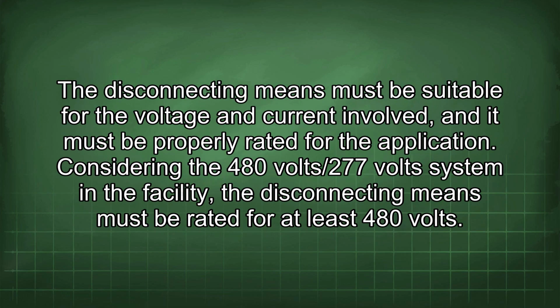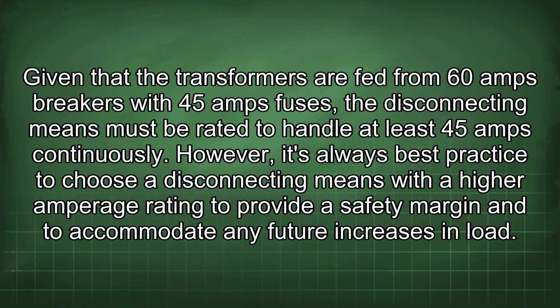The disconnecting means must be suitable for the voltage and current involved, and it must be properly rated for the application. Considering the 480 volt/277 volt system in the facility, the disconnecting means must be rated for at least 480 volts. Given that the transformers are fed from 60 amp breakers with 45 amp fuses, the disconnecting means must be rated to handle at least 45 amps continuously. However, it's always best practice to choose a disconnecting means with a higher amperage rating to provide a safety margin and to accommodate any future increases in load.